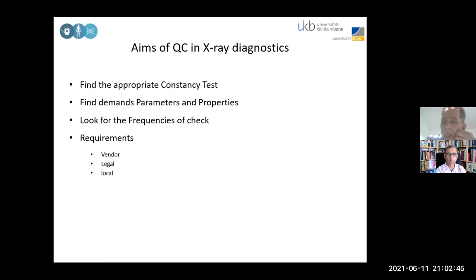So yeah, the aims of QC in diagnostics, I already pointed out quite a bit of it, but you have to find your appropriate constancy tests. You have to find them out of the legal ones, as I said, is the fourth point here. It is actually the legal ones are usually those you can't really avoid doing. But you could also find some local ones, and you could also find those which are related to a vendor. Because some tests which are required by a legal basis maybe could not apply to this machine, because this machine has certain devices which are not fulfilling those guidelines. So then you have to find a test which actually simulates or does something similar to that.